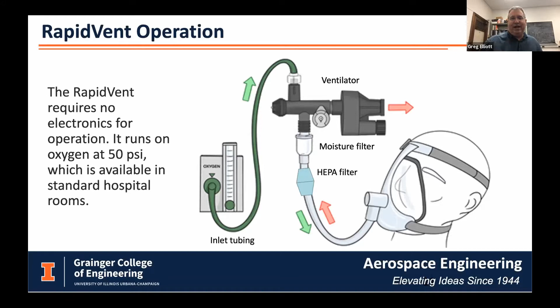Also, they had moisture filters and a HEPA filter that they would normally put in afterwards, so we wanted to make sure our device would run with those filters in place. And as the oxygen-air mixture was exchanged with the patient, we'd be able to use standard fittings and standard hoses that the hospital already had. You can see here in the upper right, you can purchase artificial lungs that you can test these devices with. It's standard operating procedure to test ventilators using these artificial lungs. Towards the upper right, you can see the pressure traces of the breathing cycles that the ventilator was able to produce in that artificial lung.